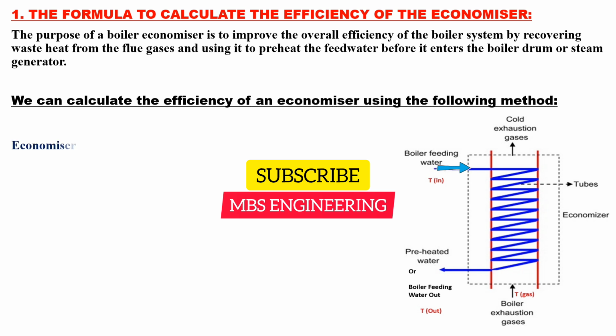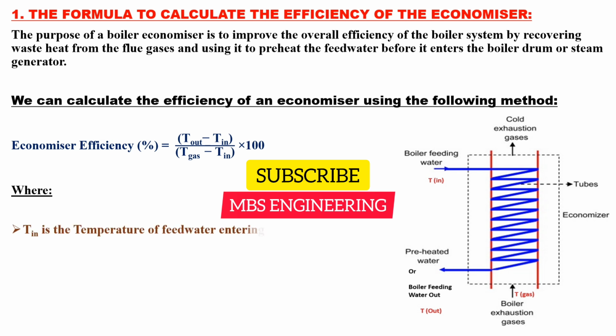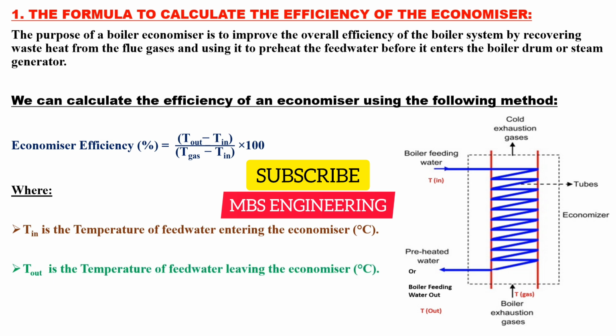Economizer efficiency in percent is equal to the feedwater outlet temperature minus the feedwater inlet temperature, and the obtained value is divided by the entering flue gas temperature minus the feedwater inlet temperature, and then the obtained value is multiplied by 100. Where Tin is the temperature of feedwater entering the economizer in degrees Celsius. Tout is the temperature of feedwater leaving the economizer in degrees Celsius. T-gas is the temperature of flue gases entering the economizer in degrees Celsius.